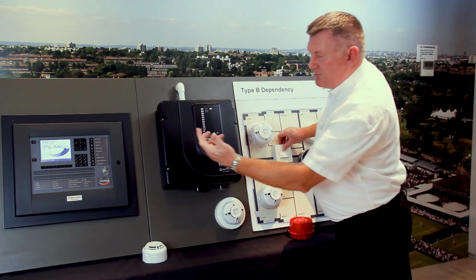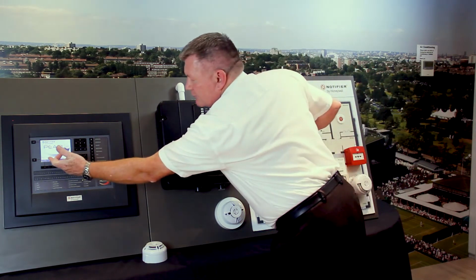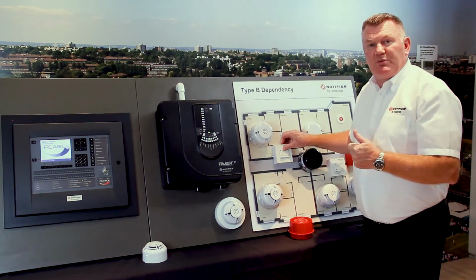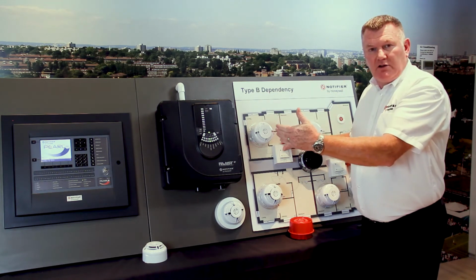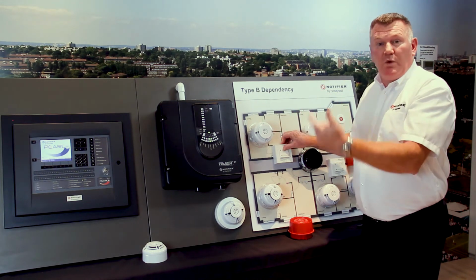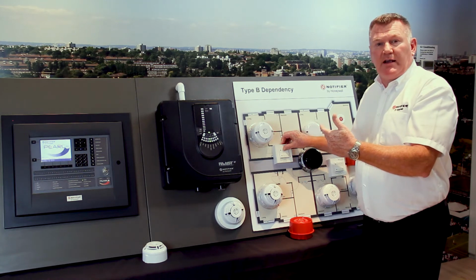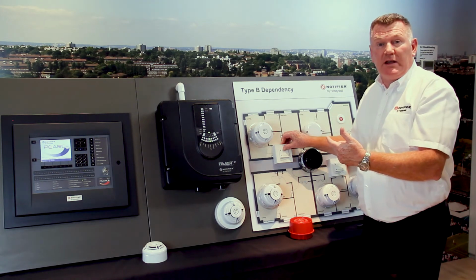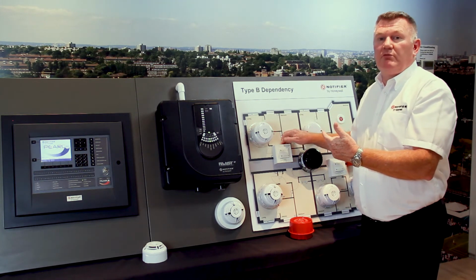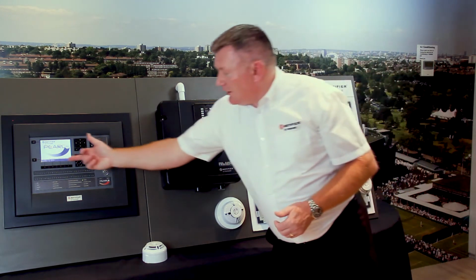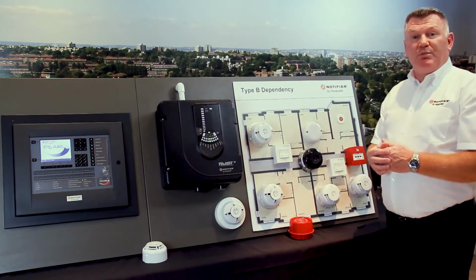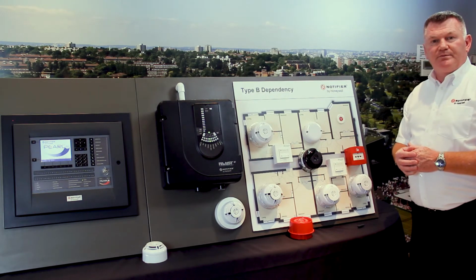What you'll always also notice, on the fire alarm control panel, we also display an auxiliary alarm. That auxiliary alarm gets entered into the control panel log, so then we know if we go back that the client or the resident has actually done a weekly fire test. I'll just release the button, that sounder will stop, and also the auxiliary alarm has now disappeared from the system.